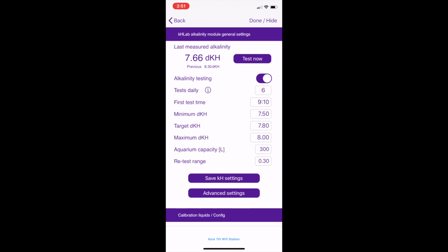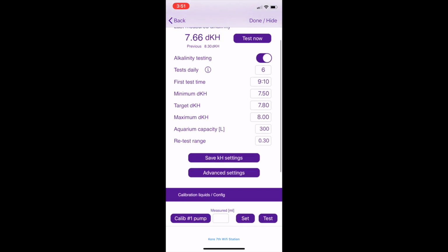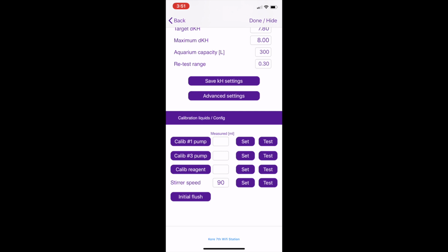So if it swings dramatically outside of what the previous test was, it will test again just to validate that it wasn't in error. Beneath that, we have the calibration specifically for pumps 1, 3, and pump 2, which is the reagent pump. If you're using the KHLab, this is where you would calibrate those pumps. The instructions for calibration are laid out pretty clearly in the manual, but just quickly to go through it, you press this Calibrate Pump 1 button whilst the output is in the measuring cylinder on the scales that are provided with the KHLab, and you will run that calibration 5 times, recording your result. You then average the result and enter the value in the measured mil box and press set.